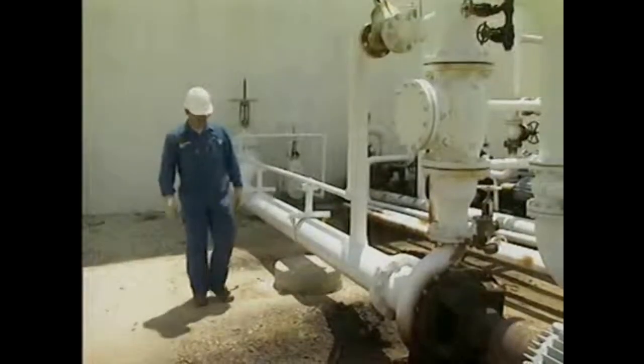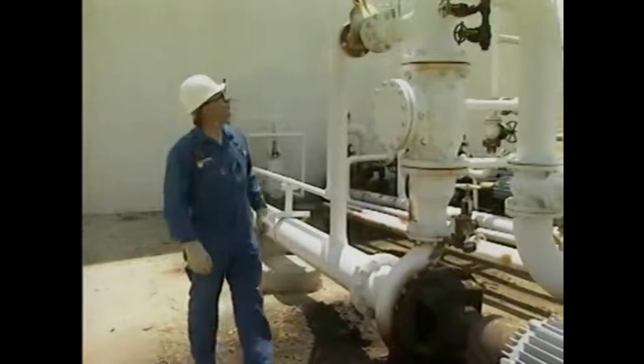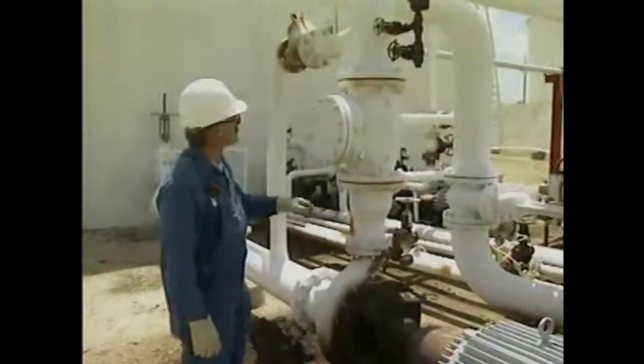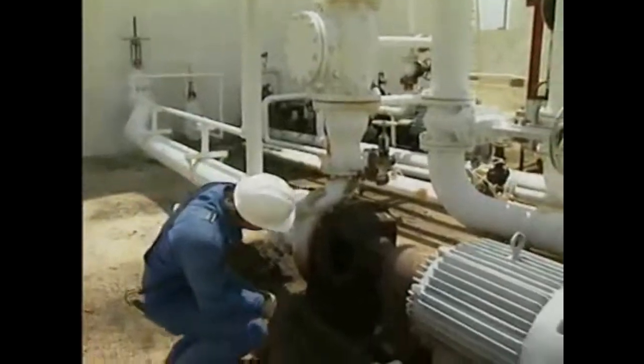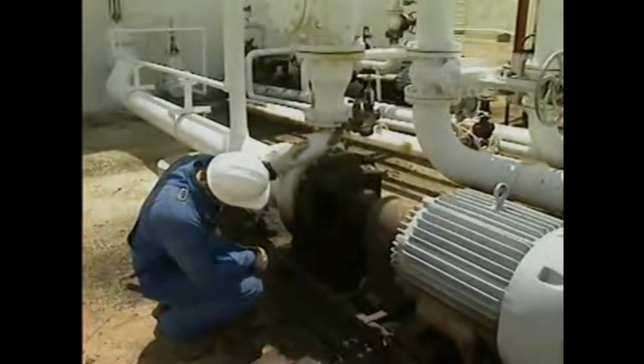The outside operator checks to make sure that the valves for the transfer pump are in the correct positions. He also checks the transfer pump for any signs of a problem. The outside operator finds nothing wrong with the pump or the valves, so the operators eliminate these components as possible causes of the problem. The operators now focus their attention on the process feed tank and its indicators.